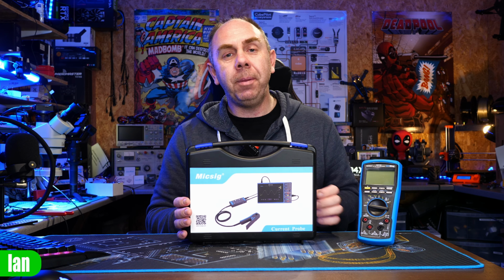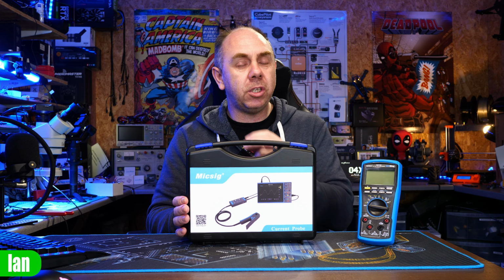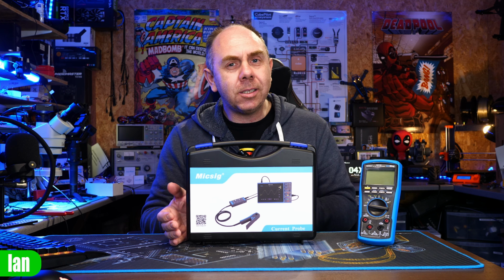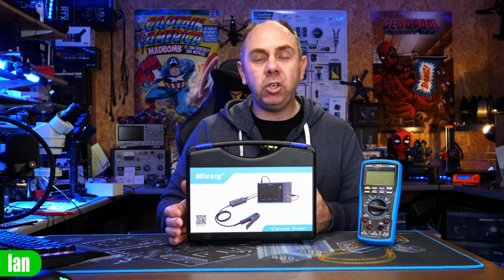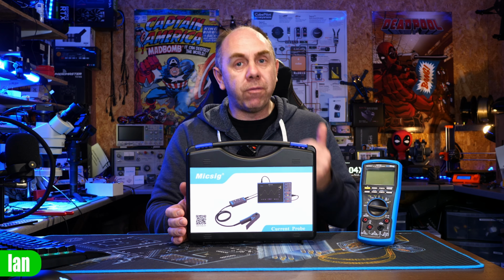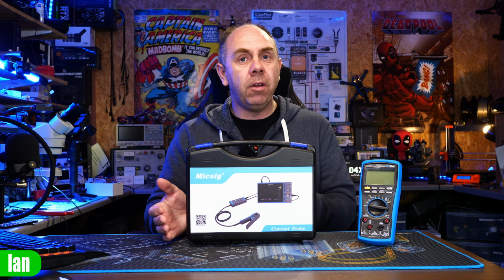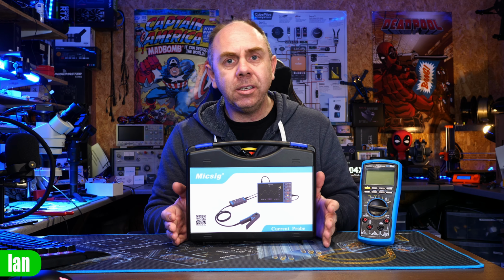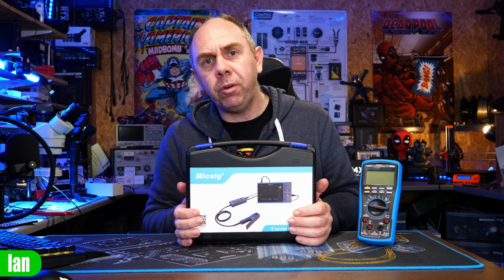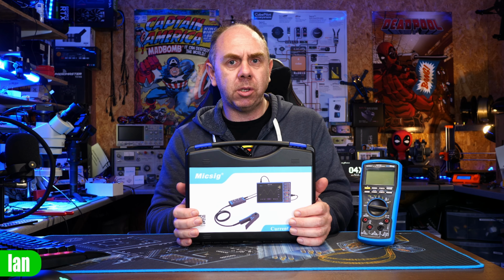A probe, such as a current probe on an oscilloscope, allows you to get a lot more detailed information because you're measuring that current versus time, and you have the ability to see things such as inrush current changes, the ability to see what the voltage versus current phase is for things like power factor, and you can even see what the switching frequency is on a switch mode power supply.